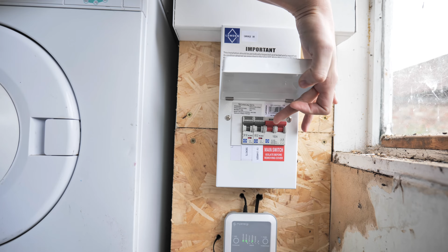Now, with this system, this house is on what's called a TT earthing system. That means there's a main earth rod — the earth isn't supplied by the main network, it's an independent earth. That means we've got to do specific things to make sure this system is protected and up to current regulations. At the mains incoming position in the house, we've got a Type S 100 mA RCD.